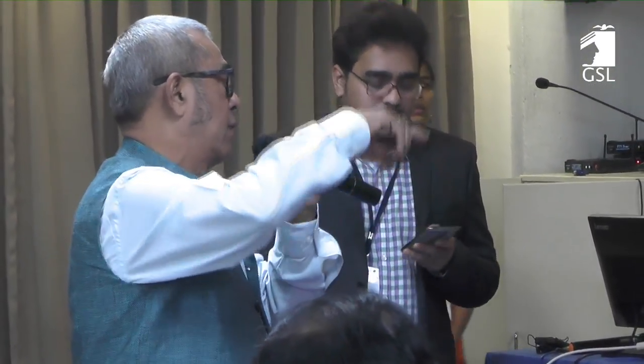Nowadays you don't need that gel thing. You can apply it anywhere, and they have dual pads. In our hospital, we have bought a Storz instrument, Storz diathermy. It has this impedance feature. It will stop coagulating however much you press, because of safety. It will stop coagulating.